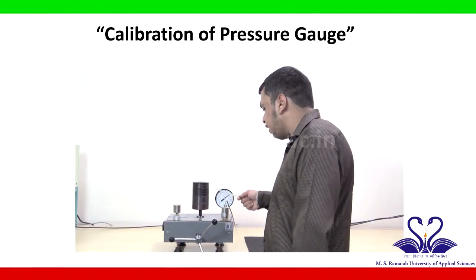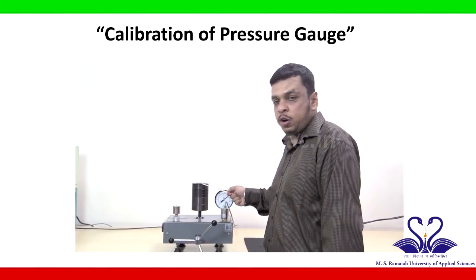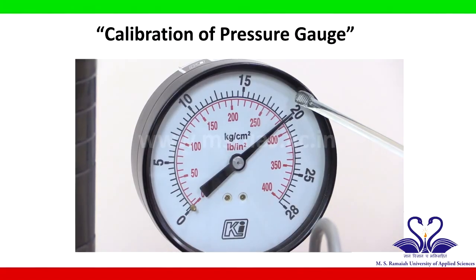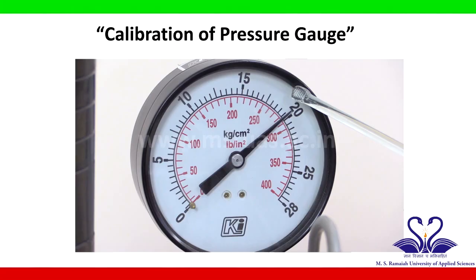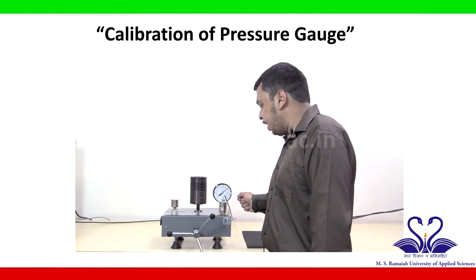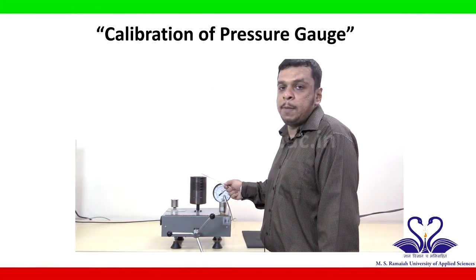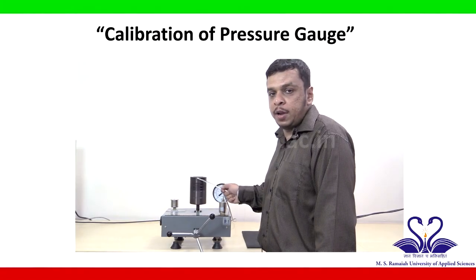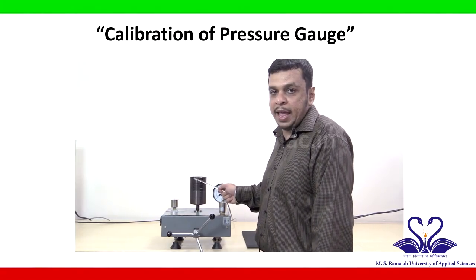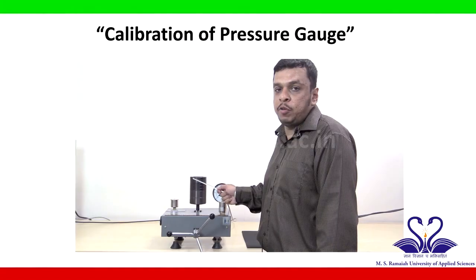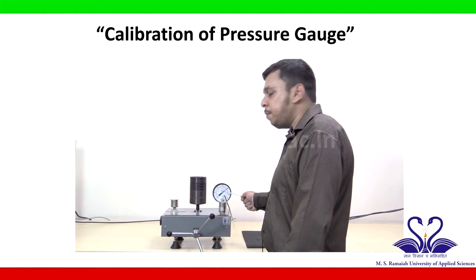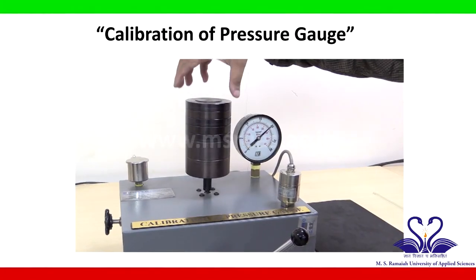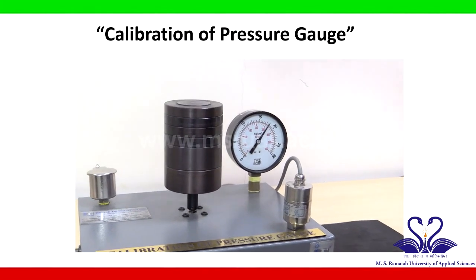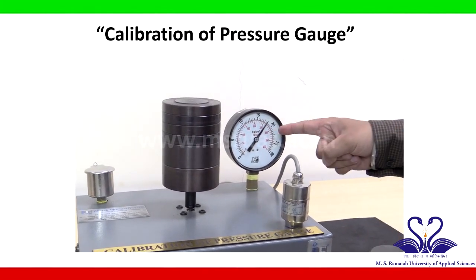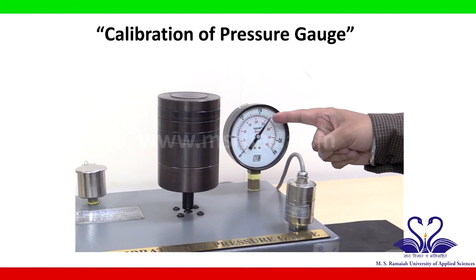Now we can see that for this particular load, a maximum pressure of 20 kg per centimeter square is being applied. Similarly, calculate the theoretically possible pressure using the formula pressure equals load by area and compare between the theoretical value and the measured value. Now we need to remove the load one by one and note down the corresponding reading being shown in the pressure gauge.